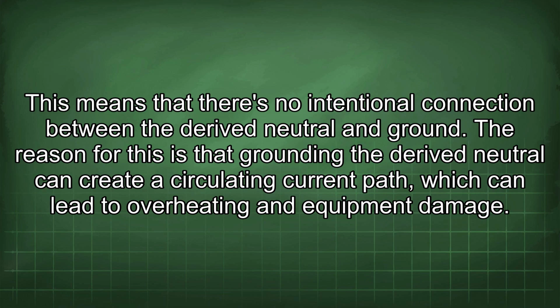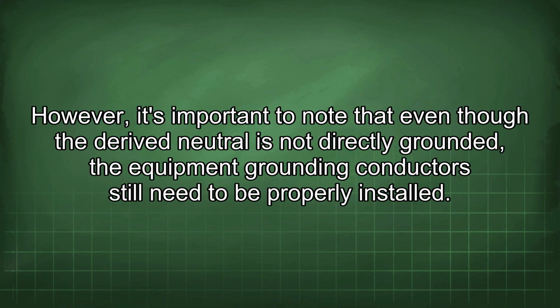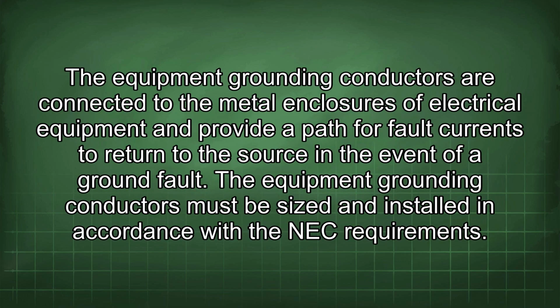The reason for this is that grounding the derived neutral can create a circulating current path, which can lead to overheating and equipment damage. However, it's important to note that even though the derived neutral is not directly grounded, the equipment grounding conductors still need to be properly installed. The equipment grounding conductors are connected to the metal enclosures of electrical equipment and provide a path for fault currents to return to the source in the event of a ground fault. The equipment grounding conductors must be sized and installed in accordance with the NEC requirements.